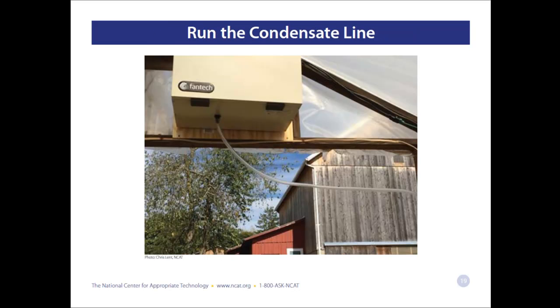Because this unit pulls moist air from the tunnel and transfers the heat from that to the incoming air, condensation does form. So there's a condensate line that allows the moisture to run out through a tube in the bottom of the unit. Now, it's best to run this tube to the outside of the high tunnel and keep that water outside the high tunnel when it does form. There is a chance in the winter, though, that that tube could freeze in really cold weather.